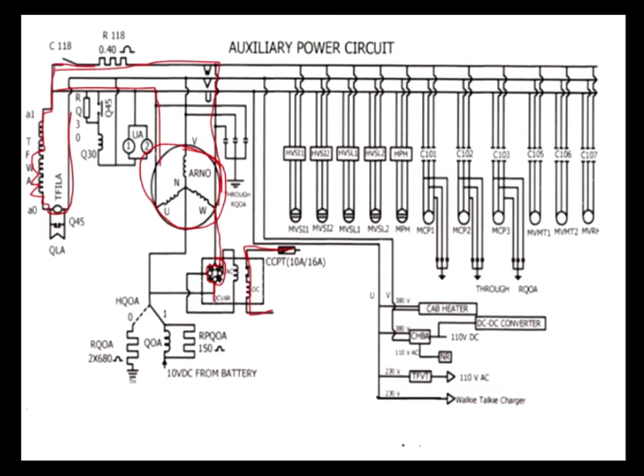So here the Arno is a rotary converter which converts single phase AC into 3-phase AC, and that 3-phase AC is supplied to MVSI1, MVSI2, MVSL1, MVSL2 and MPH, provided their switches HVSI1, HVSI2, HVSL1, HVSL2, HPH are in 1 or on 3 position. So here, along with Arno, 5 direct motors will start, and the function of MVSI1 and MVSI2 is to cool the RSI blocks. Function of MVSL1 and MVSL2 is to cool the SL's smoothing reactor, and the function of MPH is to circulate the transformer oil.